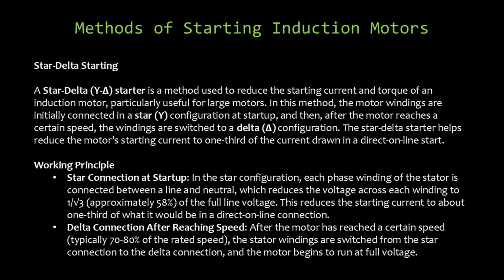This clever arrangement reduces the voltage across each winding. Once the motor reaches about 70 to 80% of its rated speed, the windings are switched to a delta connection, allowing the motor to run at full voltage. It's a strategic approach to managing motor startup challenges.